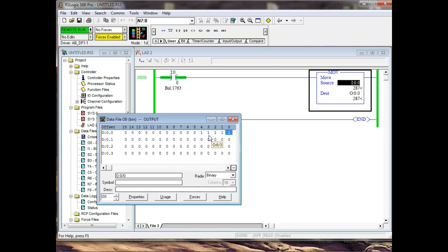So I'm taking the input switches and moving them directly to an output port. That's as far as this one goes. It's only got 10 inputs, 0 to 9. So you could use a move instruction to get information from input devices, right? You understand? And then take them to an output port if you wanted to, or take them into a storage location, or do math with them. There are all types of options available with this move instruction. Very powerful instruction. Every PLC that I've ever programmed has one of these, a move instruction. Are we okay? Yes, no?